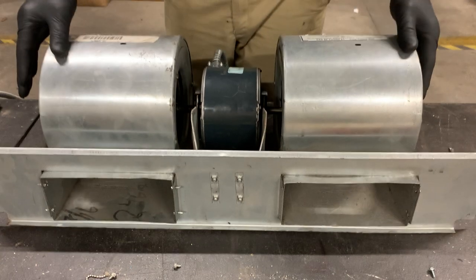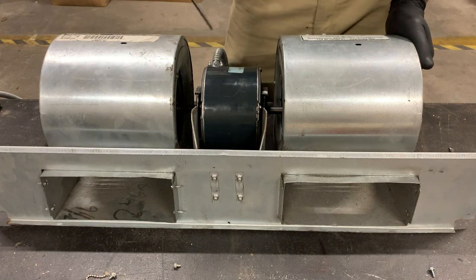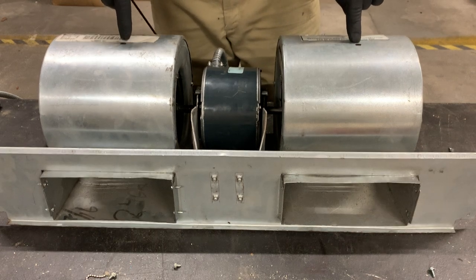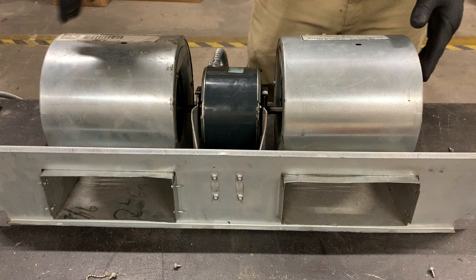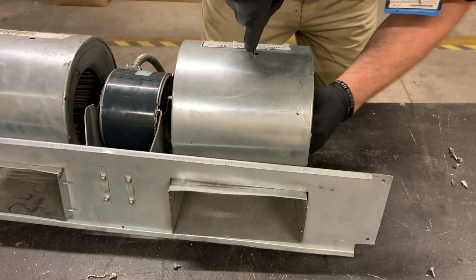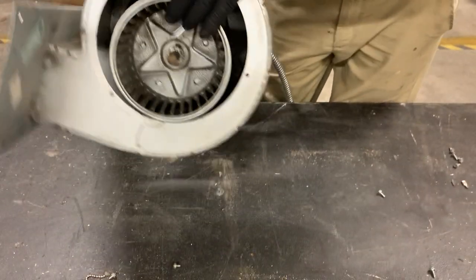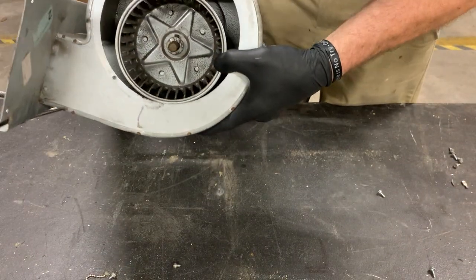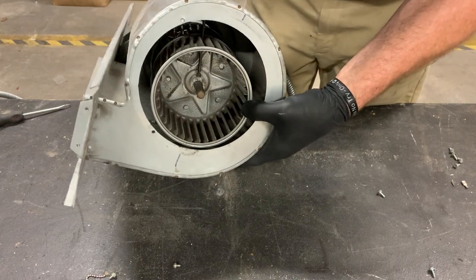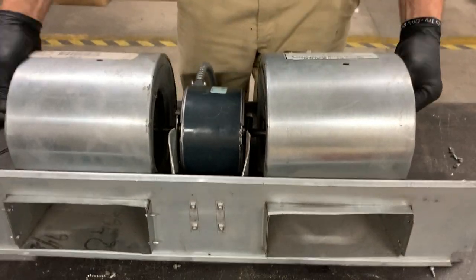What I've gone ahead and done is I've loosened up the squirrel cages on the inside. Mine are a 5/32nd Allen wrench — the T-handle's the best to use. You've got two holes here at the top. You put your T-handle down inside and line it up with the set screw that's inside holding your squirrel cage in. These are on the inside, just like this. So you're going to take your T-handle, stick it through there, and line it up with the set screw.